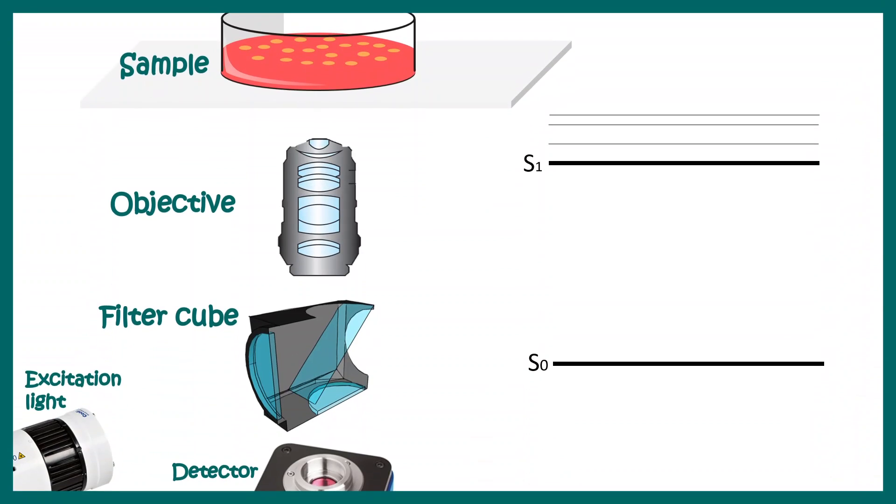Now let's focus on the light path. The light comes from a light source, which might be a mercury lamp or an LED source. The light passes through this filter cube and then gets diverted to the specimen through the objective lens, where it is focused on the specimen via this objective lens.